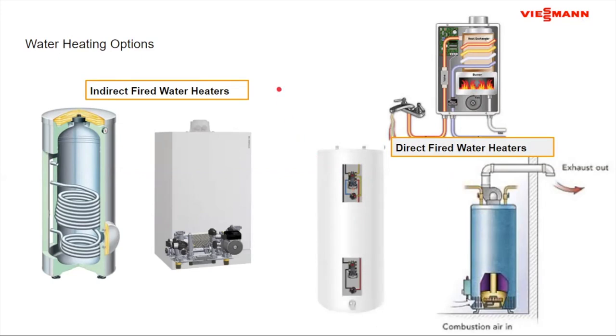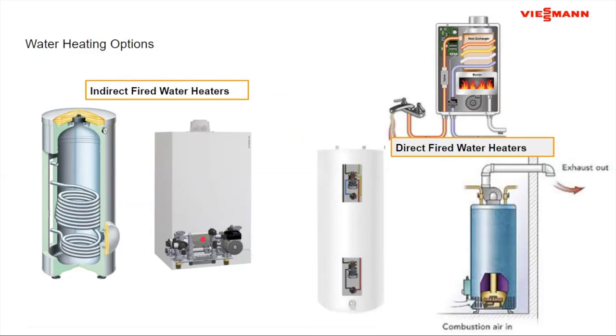When I go indirect fired, the domestic water isn't really in contact with the source of heat. So over here, I have a tank-style indirect water heater. Hot water from the boiler is passed through the coil, indirectly heating my domestic hot water. And over here, I have a plate heat exchanger, again, where the boiler water passes through and generates the hot water. Now, when we look at indirect fired methods, there are a lot of advantages to it.